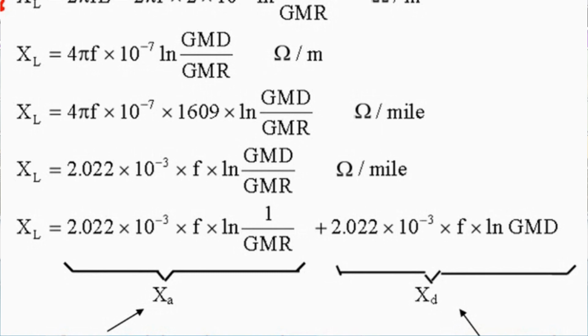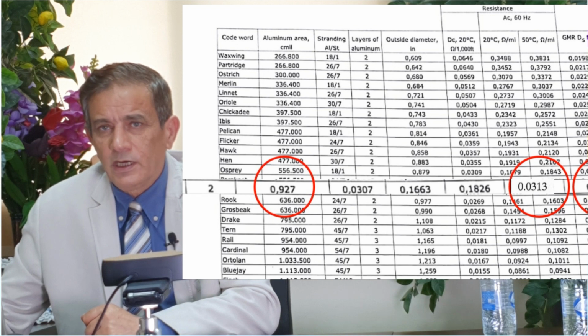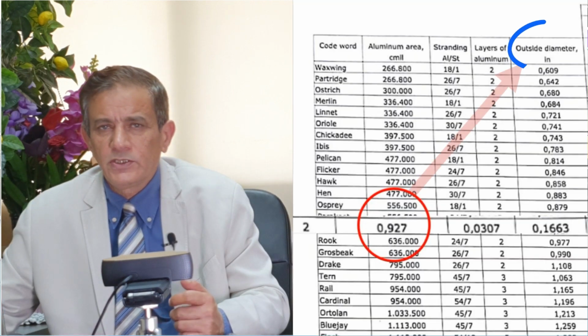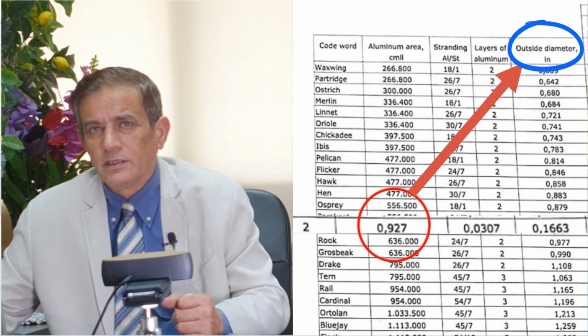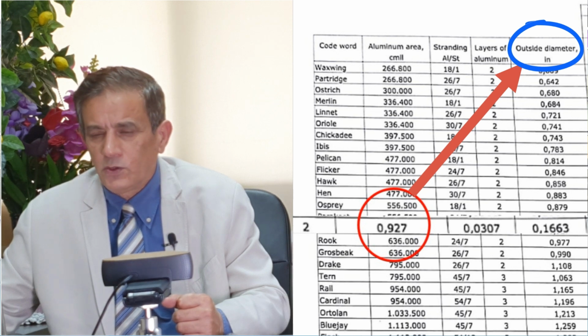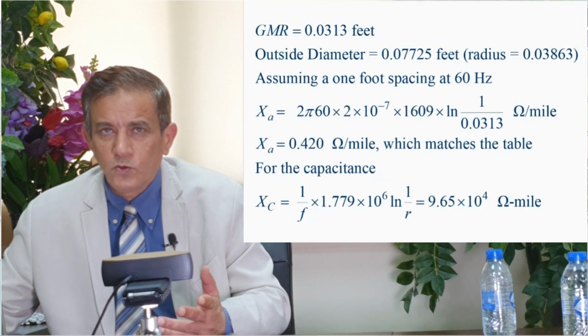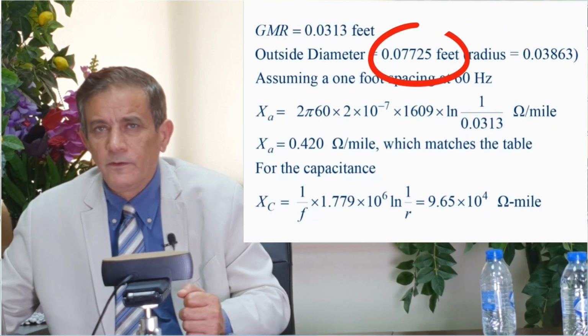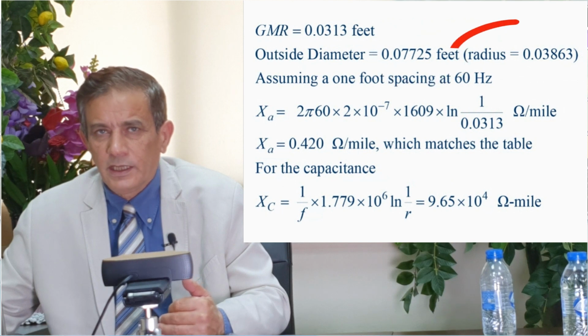Taking this example, this is a cable given the code Osprey, and here is the information given: GMR is 0.0313. Geometrical mean radius is the information the manufacturer gives you. The other part you calculate based on your system. This 0.927 is the diameter, given in inches. You convert it to feet, 0.07725, then divide by 2 to get the radius.